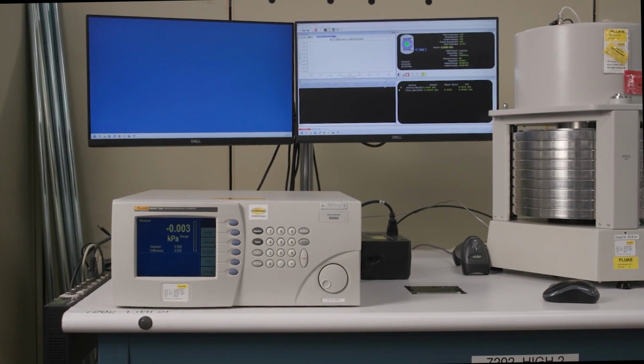Once the test concludes, the system generates a certificate and the DUT is moved forward for review. From setup to certification, precision is maintained at every step. And that's it. That's how you calibrate pressure with a piston gauge.